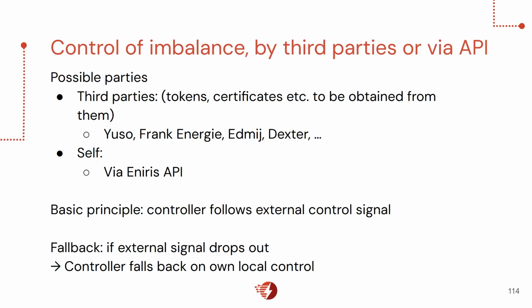For the last mode of control, control by a third party or through an API, these are added in the external signal controls tab. These can be third parties, or you could do it yourself using our Eniris API, which is a public API you can access to send set points yourself to our controller, which sends them to the different assets. The thinking is that we always follow your signal, or the signal of the third party, and only if the external signal drops out do we fall back to the local control mode we just discussed.